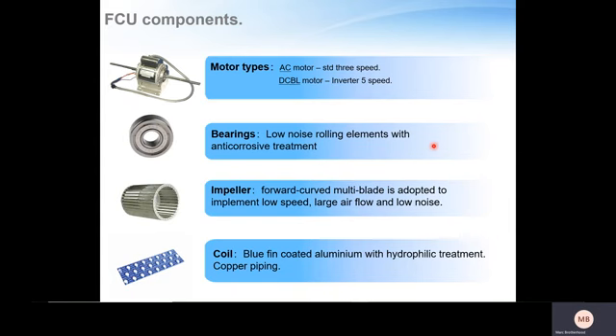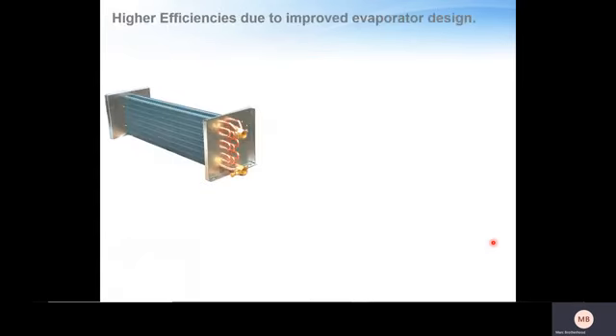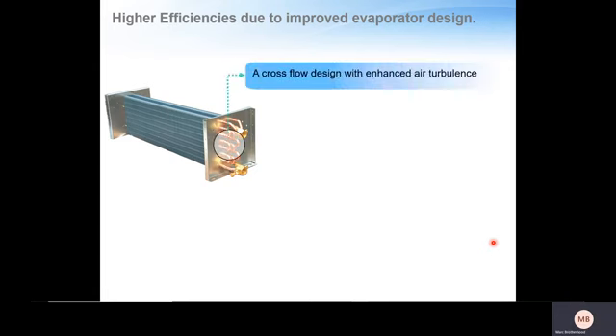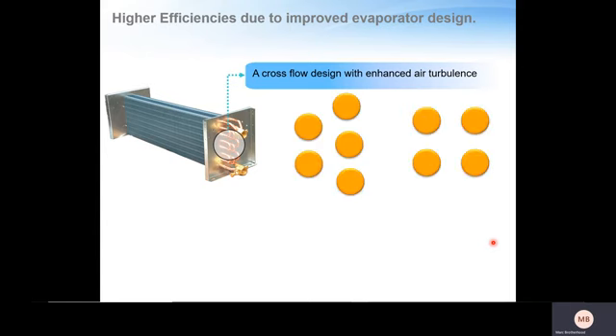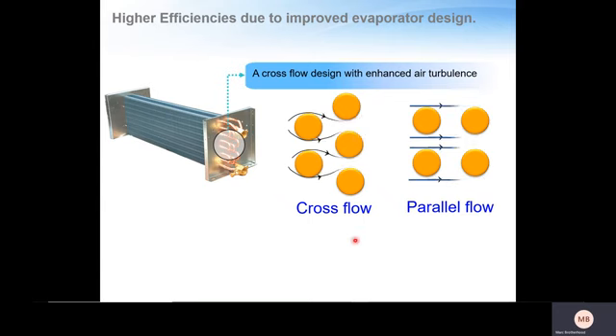And the coils are bluefin coated aluminium with hydrophilic treatment and copper piping going through the centers as your carriers of your working fluid. The hydrophilic treatment pretty much makes the water molecules not coalesce and run off very easily off the surface, so it always ensures that there's no water acting as an insulation barrier, so you're getting high efficiencies with great delta T's with the air molecules when they cross the fins. Higher efficiencies also due to improved evaporator design. So if we look at this design of this Daikin unit, a cross-flow design has been created to increase air turbulence. So if we look at this typical cross-flow design, which Daikin has incorporated compared to conventional parallel flows, this allows for a lot of destratification of the air and nice mixing of the air molecules so they can release their energy onto these cold coils and therefore cooling the air.